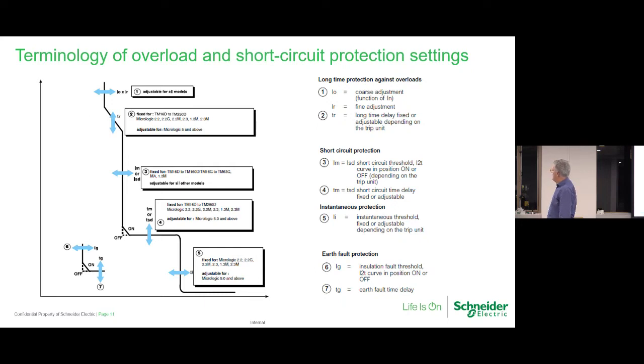Terminology of overload and short circuit protection settings. There's a lot of settings on some trips, and there's not many on others. So long time protection, I mentioned IR. But there's also another one called TR, which is the time delay on the thermal setting. This here is invariably not used in the mid-range of the network, but is often used in the source breakers. But it's good to know that it's there.